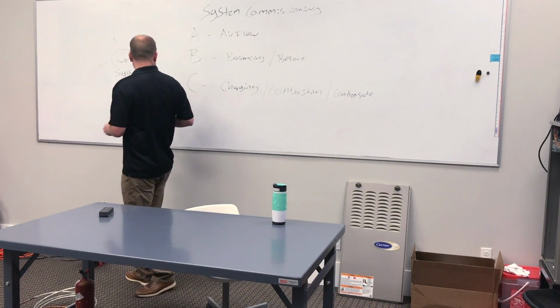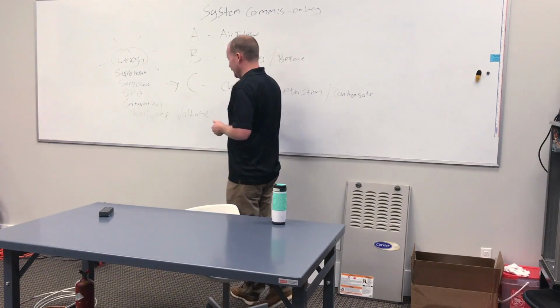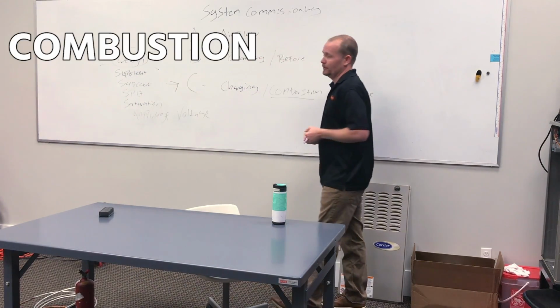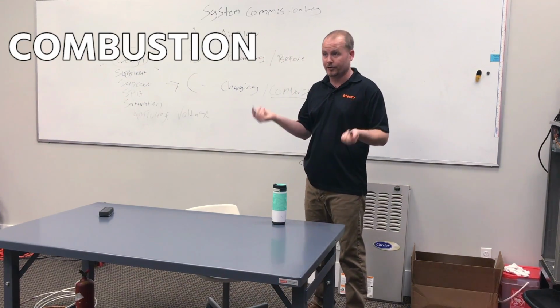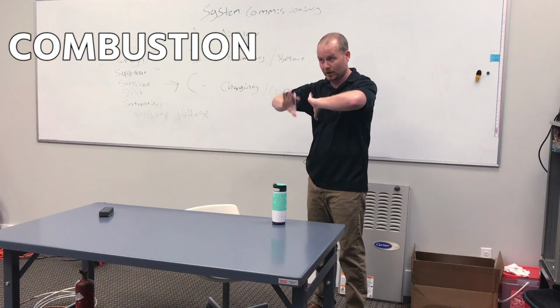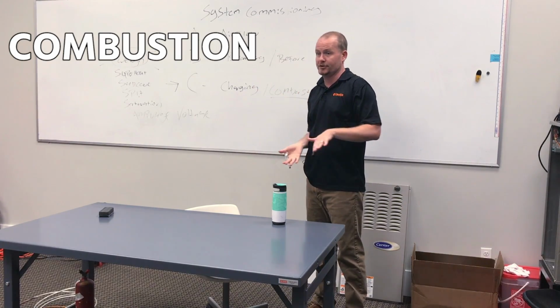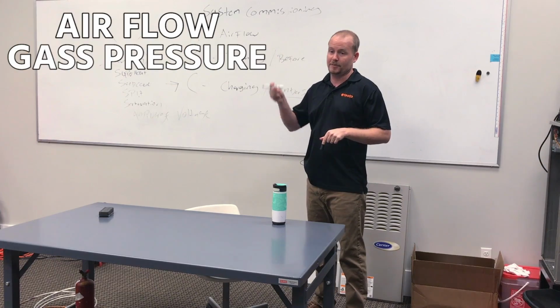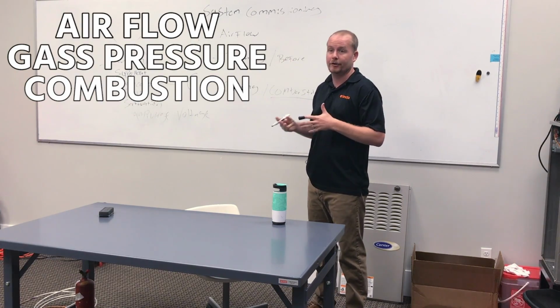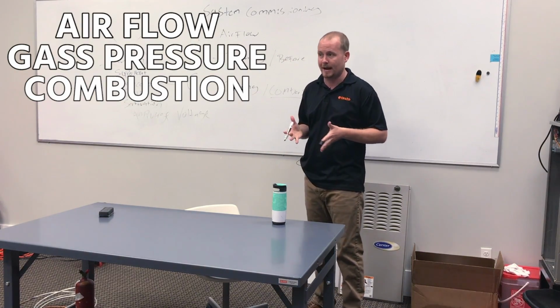So amperage and voltage, and then finally, if you're doing a gas furnace, we have to think about combustion, which starts with checking gas pressure, and then you go into the combustion analysis, which again, policy is when we do a gas furnace, we're doing a commissioning afterwards. Airflow, gas pressure, combustion. I want you all to know how to do that eventually, but that's a slow thing, so mostly Max is going to do that for now.